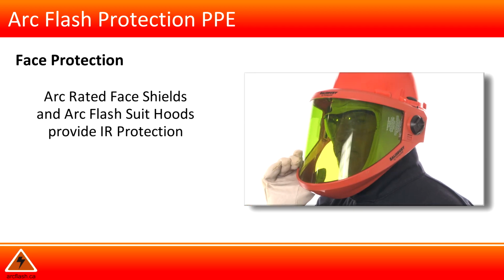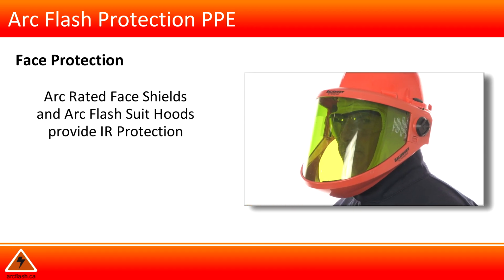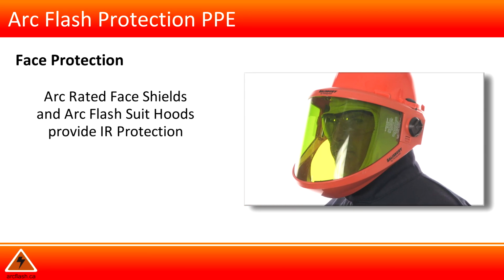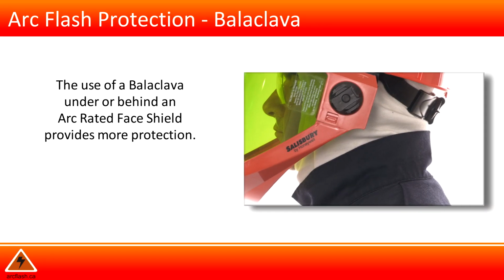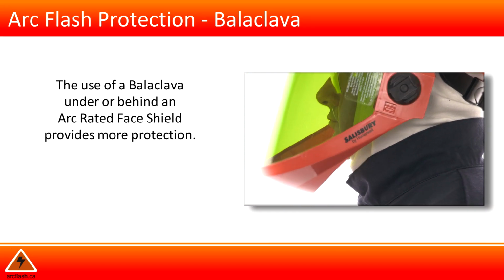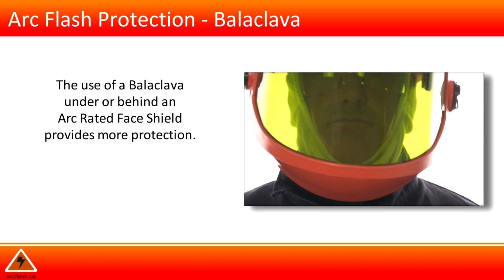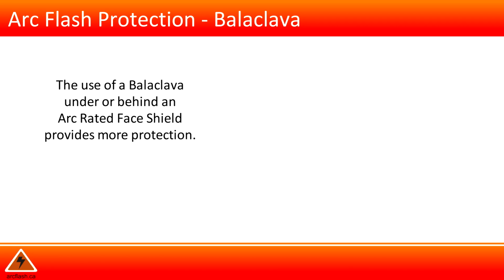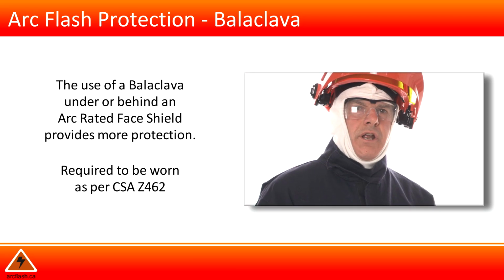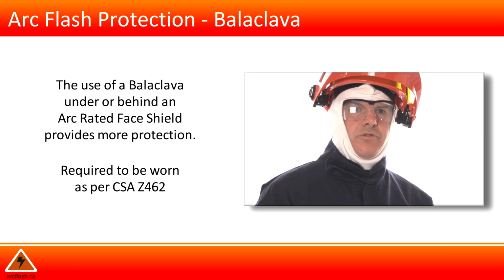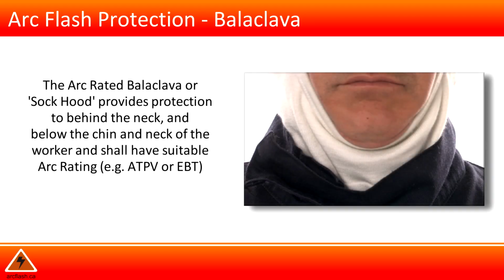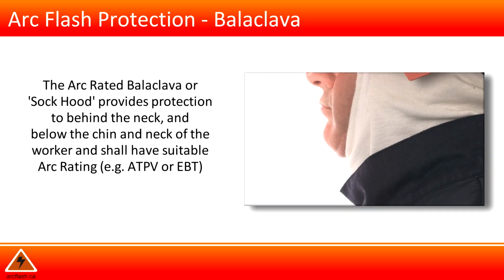Arc-rated face shields and arc flash suit hoods provide infrared protection also. The use of a balaclava under or behind an arc-rated face shield provides more protection, and is required to be worn as per CSA Z462. The arc-rated balaclava or sock hood provides protection to behind the neck, below the chin and neck.